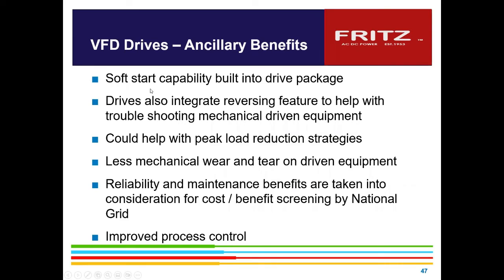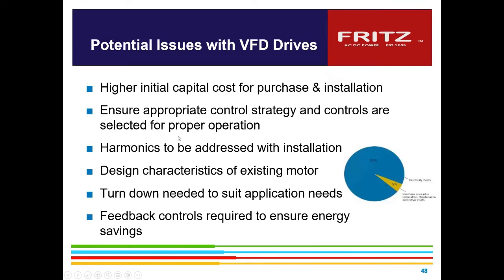Some other benefits are that they do soft start and soft stop of the motor. If you like, you can program that in, which eliminates issues with water hammer and surging in piping systems. You can strategically do load control. So at different times of day, on higher loads of big motors, you can slow the process down a little bit and get power savings that way, but also get demand savings for the power company, as we become more and more into the demand of power around the world.